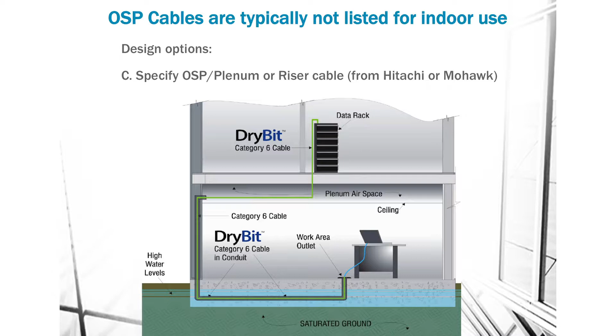And then, as you mentioned a few minutes ago, the other option is to spec out a specialty cable that's both outside plant and indoor rated. So Hitachi just released a cable that's outside plant and wet rated. I don't know if it has a shield on it. I can't remember, so I'll have to go back and check on that. Mohawk makes one that's just CM rated, maybe even riser rated. That's also outside plant. So those are the two you can look to, so you can avoid that transition point or extending expensive conduit through your building.